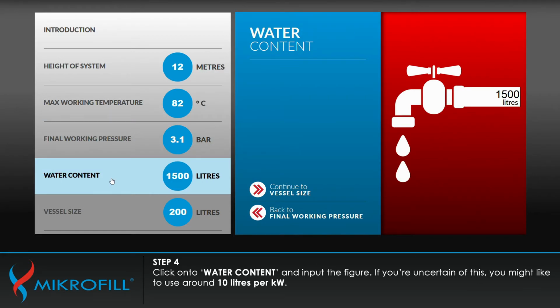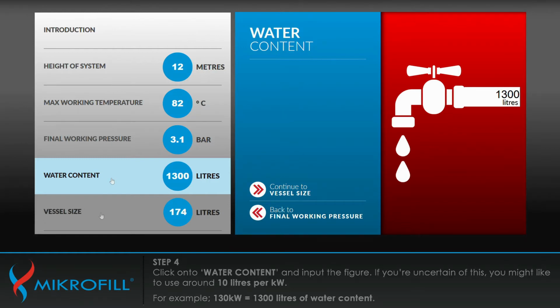If you're uncertain of this, you might like to use around 10 litres per kilowatt. For example, 130 kilowatts equals 1,300 litres of water content.